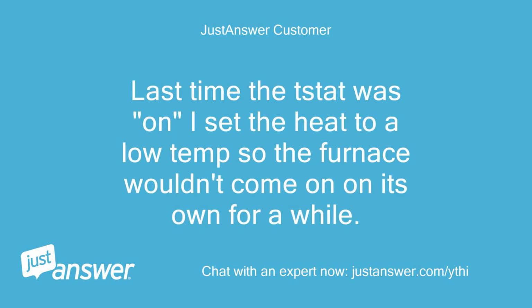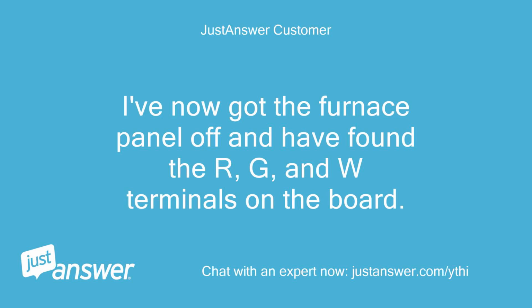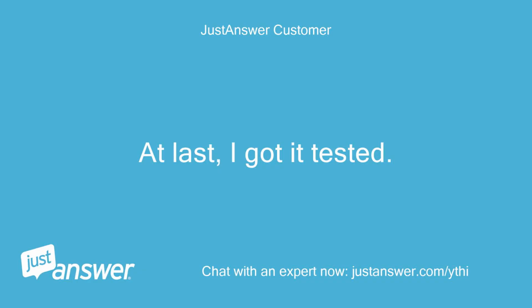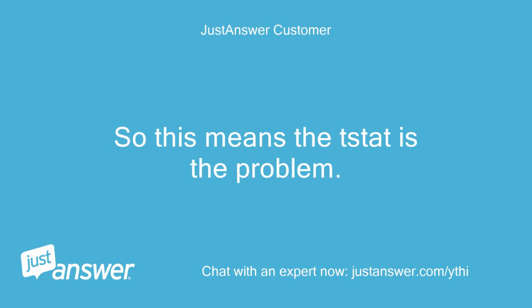Last time the tstat was on, I set the heat to a low temp so the furnace wouldn't come on on its own for a while. But I haven't turned off any breakers or anything. I've now got the furnace panel off and have found the R, G, and W terminals on the board. So I'm just going to touch the R and W on the board and see if the furnace kicks in? Okay, let me know how it runs, Russ. At last, I got it tested. Jumping R and W kicked the furnace on. So this means the tstat is the problem.